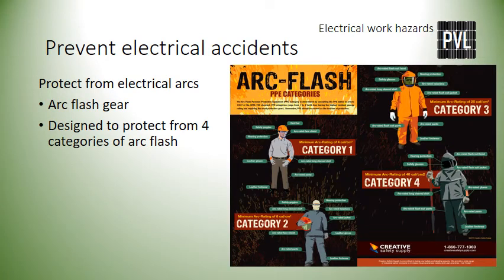The NFPA 70E is a publication with recommended guidelines for safe electrical work practices. Arc flash gear is PPE designed to protect from various levels of arc flash. Arc flash gear is a determined set of PPE required to wear during work on live equipment and live wiring. At a minimum, arc flash gear includes insulated gloves, leather gloves, protective clothing, leather shoes, safety glasses, hard hat, and face shield.